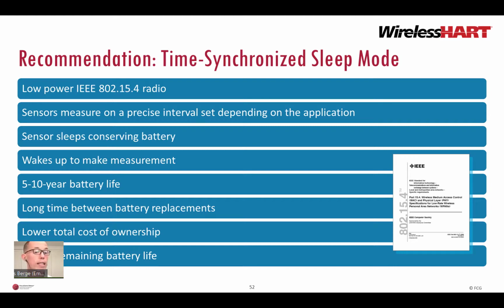The sensor wakes up briefly to make a measurement, then goes back to sleep again. As a result, WirelessHART can achieve 5 to 10 year battery life for sensors. So you seldom have to replace the battery. This means lower total cost of ownership.